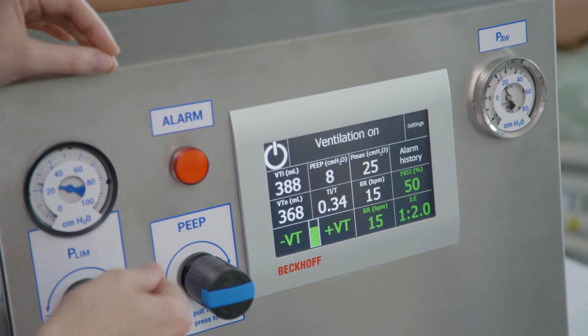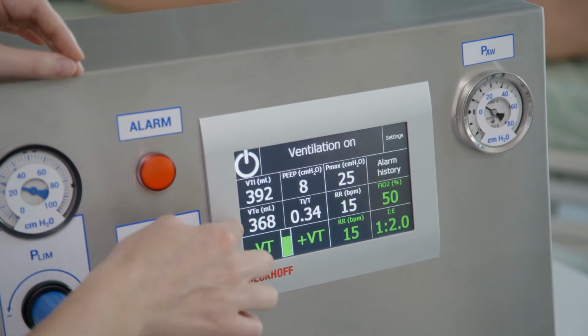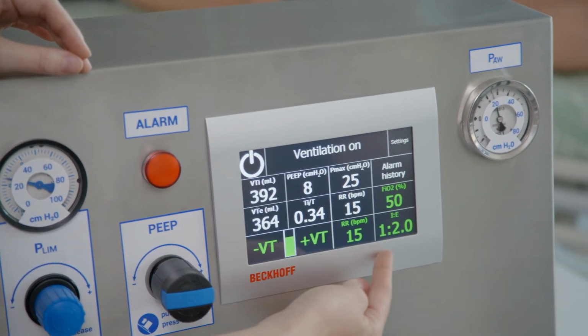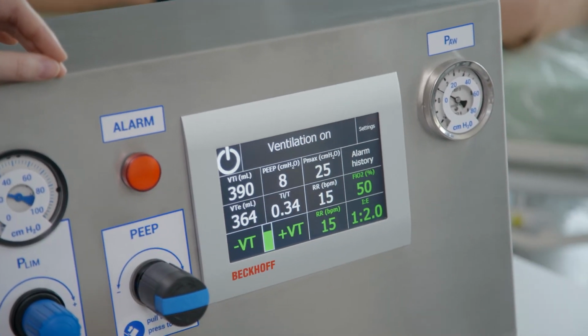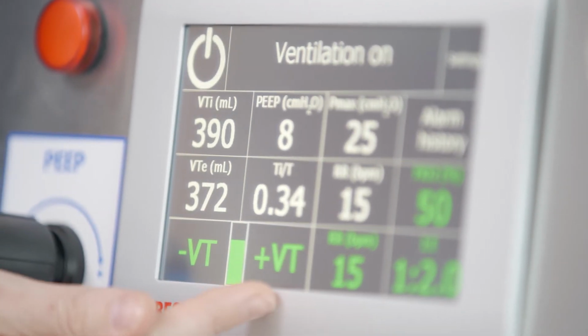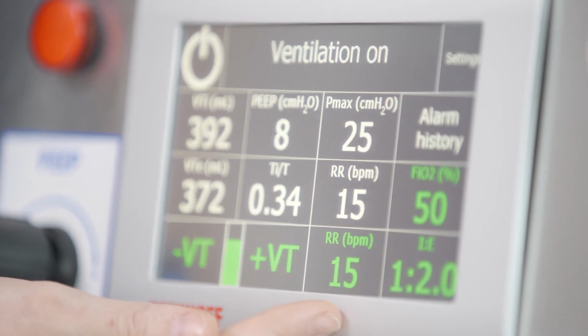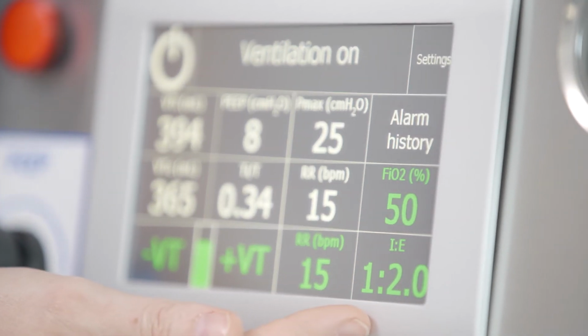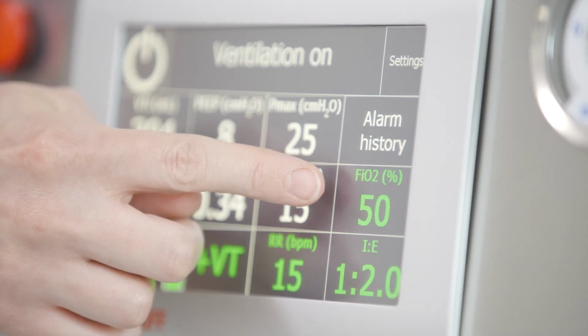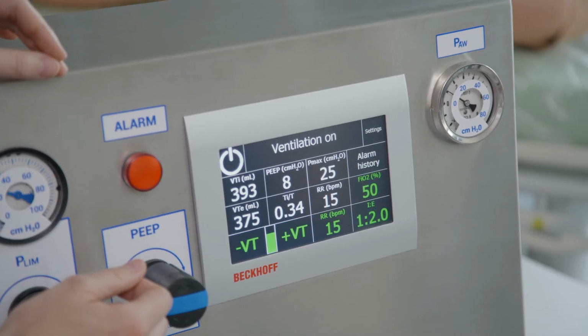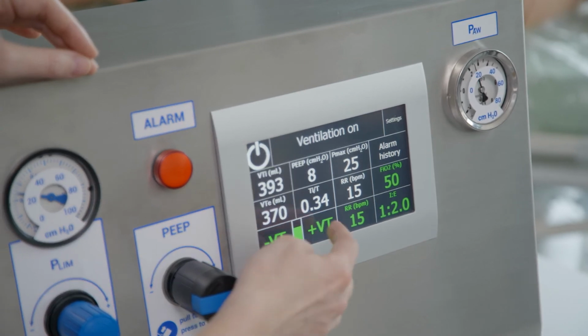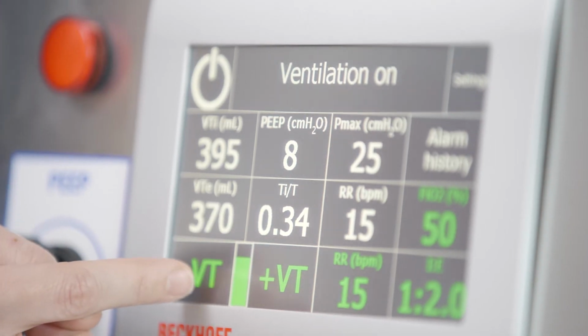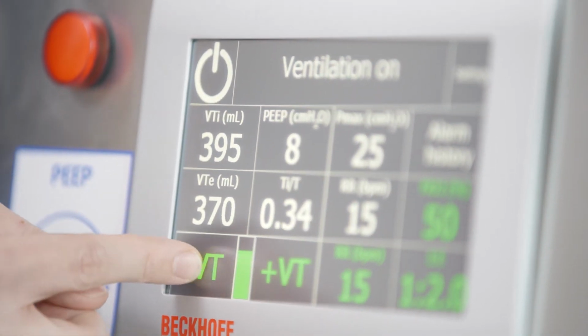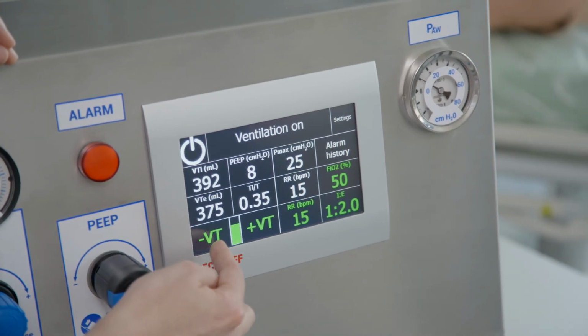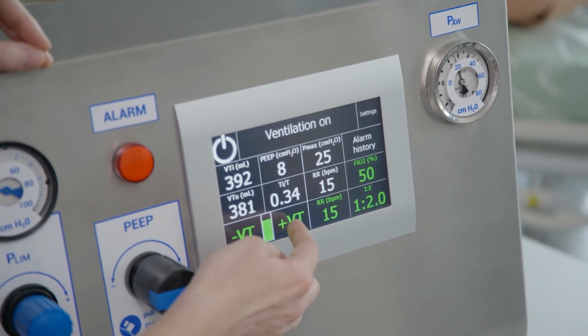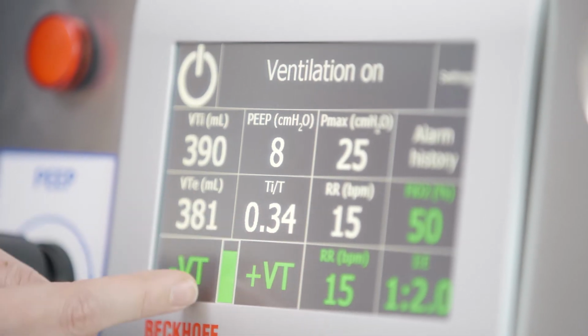The main screen has white figures with measured parameters and green figures with adjustable ventilation parameters, including tidal volume, respiratory rate, inspirium to expirium rate, and the fraction of inspired oxygen. The tidal volume can be increased by selecting VT plus and decreased by VT minus. The change of the tidal volume will be displayed during the next breathing cycle and is displayed by the green indicator.